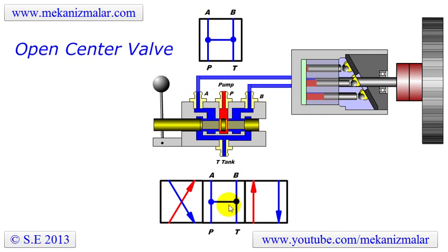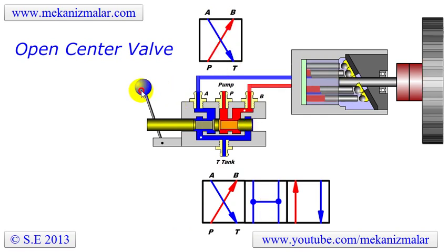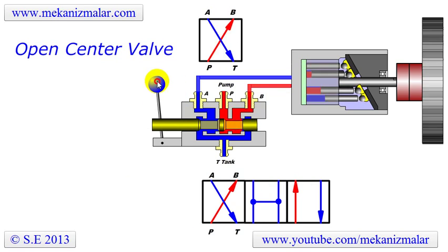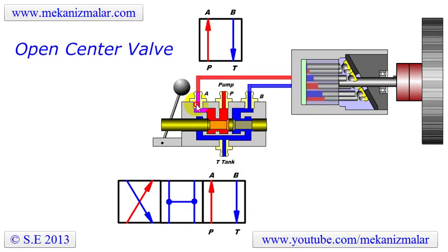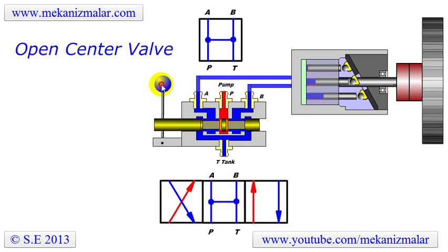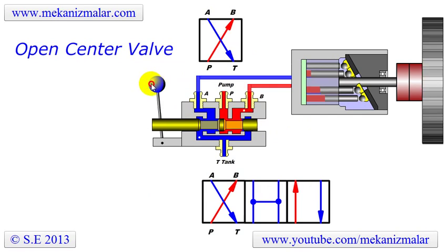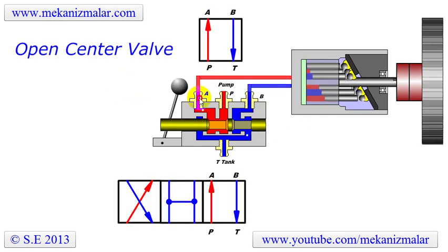The corresponding flow diagram representing the center position of the spool is shown at the top. The bottom diagram shows three square blocks which represent each position of the valve and how they are combined to create the flow diagram of the valve. This valve is commonly used for motors because it handles system overloads or shocks to the system, and for this reason it is sometimes called the motor valve.